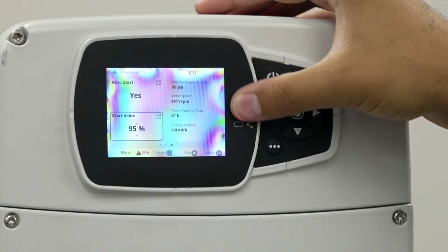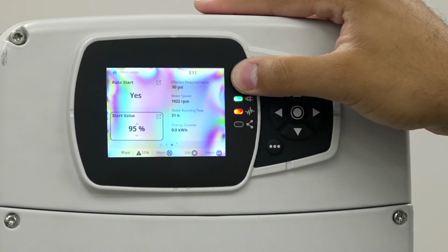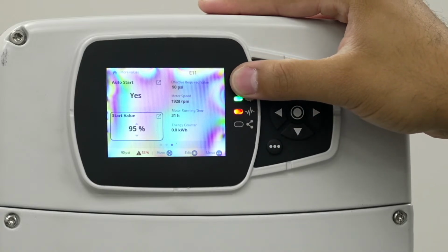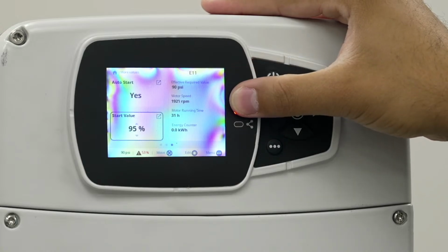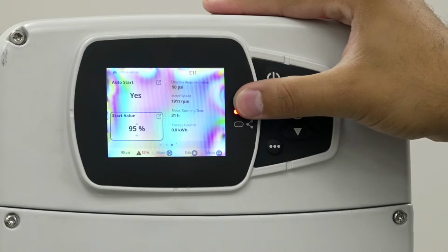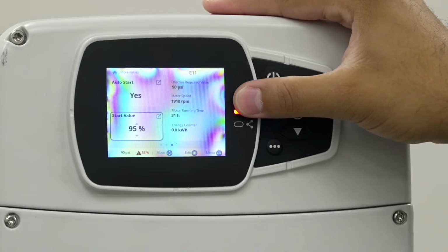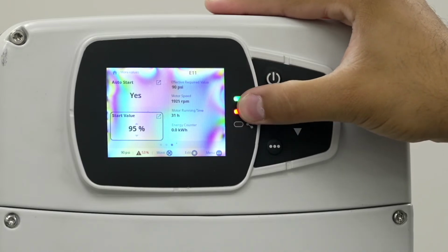But it's also giving you some valuable information on this screen. It's telling you the required value, so that's what you have your pressure set at. This is the current motor speed. You can see that fluctuating as if it's slowing down or speeding up to maintain the constant pressure. There's runtime.